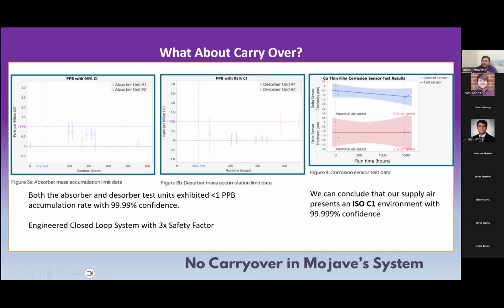And finally, on the right, what you see is we did have in the field itself, there's another rep in another state that had one of these systems in their building for 2.5 years and put a copper thin film corrosive strip on there. And after 2.5 years, it looked pristine. So again, we can conclude that our supply air presents an ISO C1 environment with 99.999% confidence. So for those that are concerned about carryover, I certainly understand the concern.